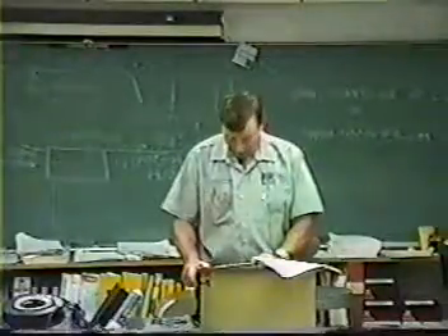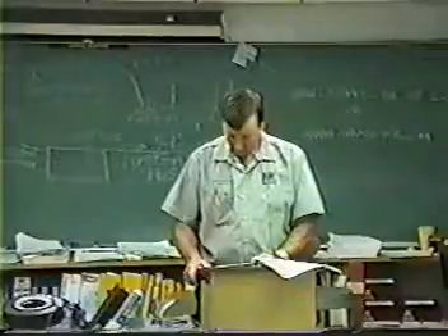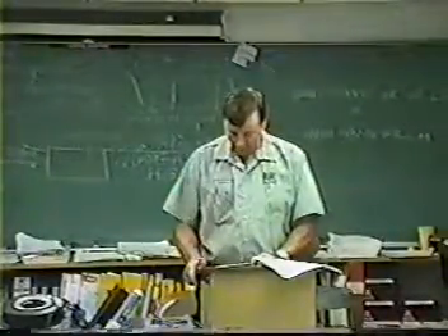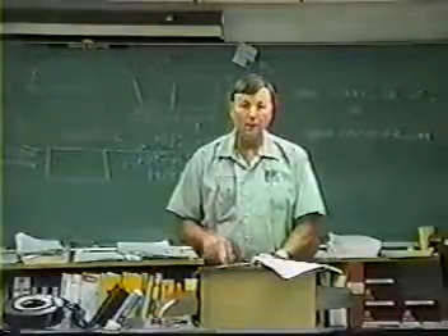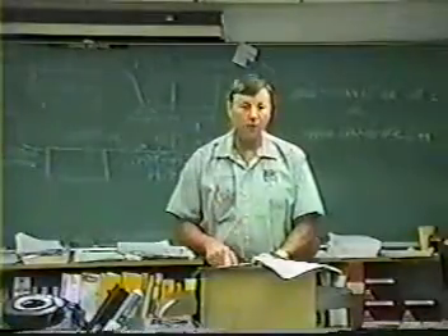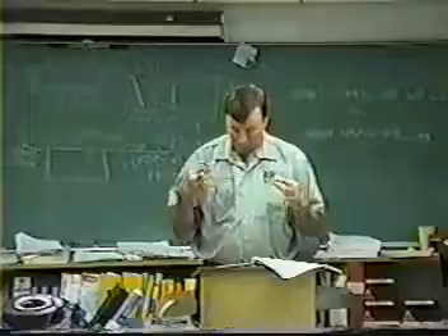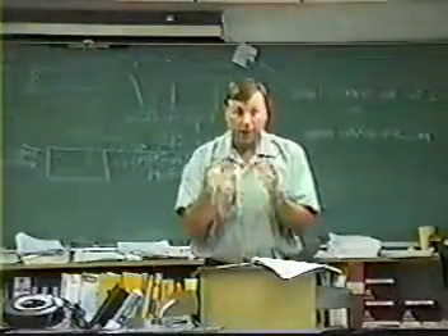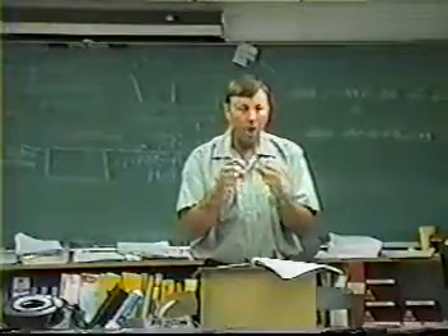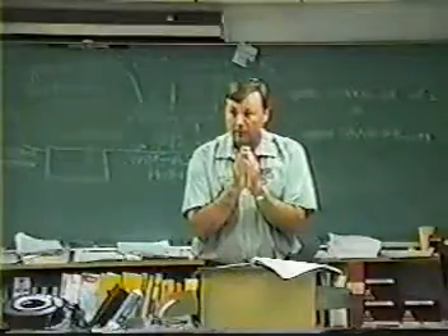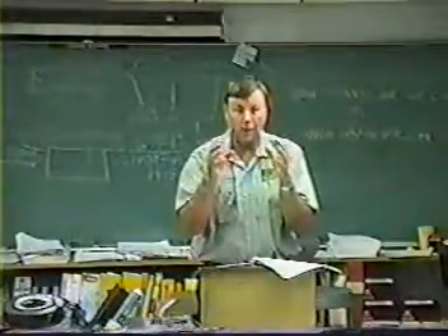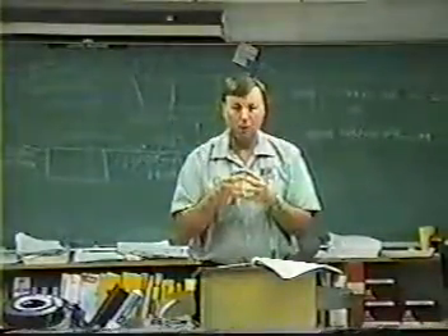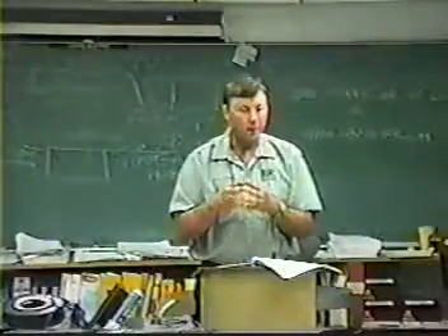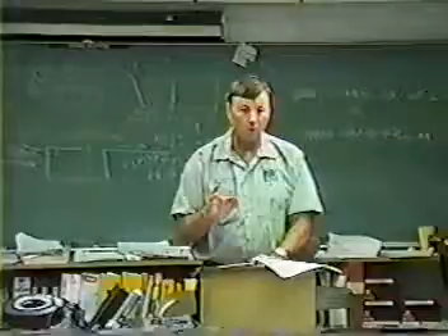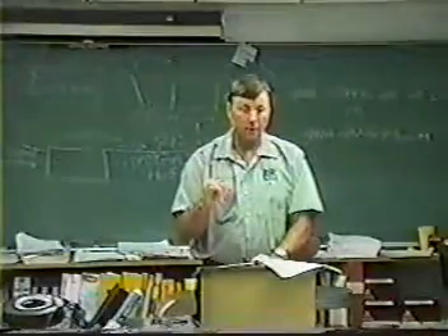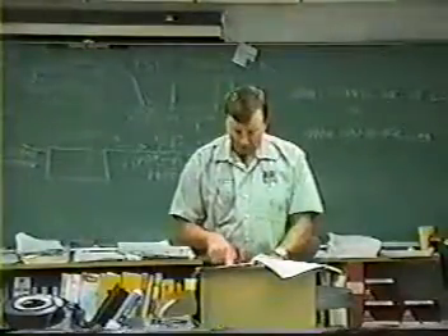A hermetic compressor relies on the flow of refrigerant for cooling. Energizing the compressor under vacuum can damage the motor winding. They have been known to blow up as well. It's an effect called the corona effect. How many of you have ever heard of the corona effect? If a hermetic compressor is under vacuum, you have nothing at all to separate the electrical voltage, so it can literally arc together, and it can explode and blow up. It blows the terminals out of the compressor. I've seen them separate before. That's called the corona effect. Now, it may not be on the test, but it's just good information to know about. I've seen it listed one other time that I can remember, but it's very critical that you never energize a hermetic compressor under a vacuum.